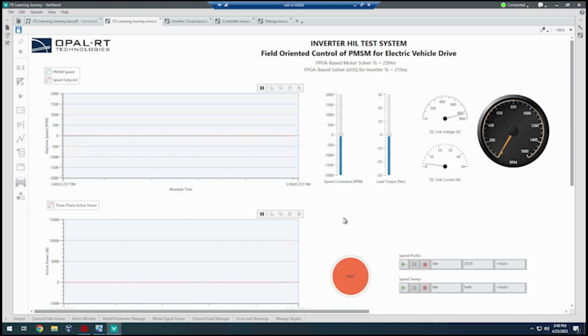In this case, my inverter does not detect an overcurrent fault and continues to control the machine as best it can. But in the real world, we would catch this fault and say that the inverter should turn off within about a millisecond of detecting this overcurrent situation. This is a really good use case to show how you can use scenarios directly in your test cases to ensure your inverter covers them.